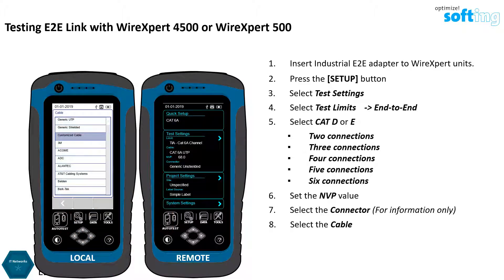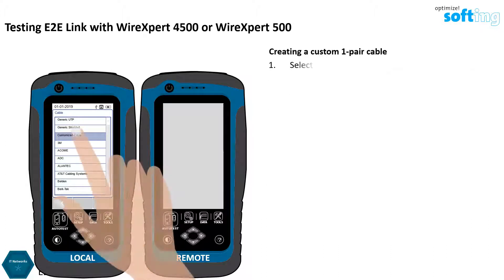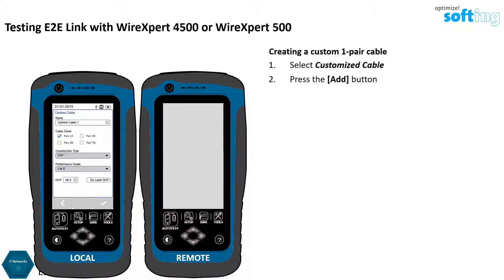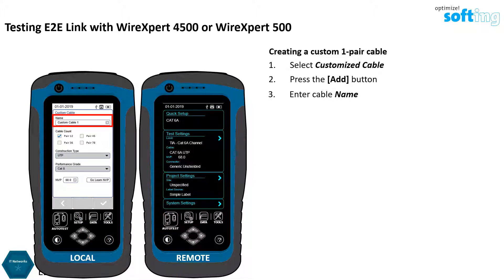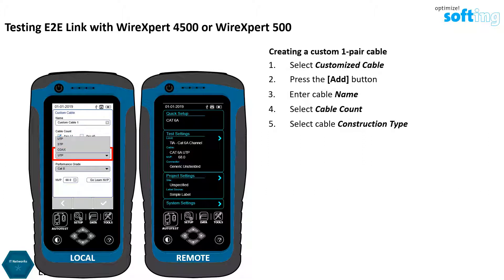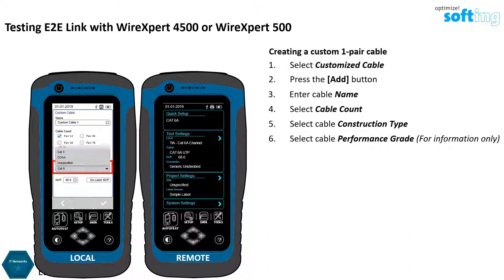The limit sets are dependent on the number of pairs in the cable to be used. 2-pair configurations can be found in Generic UTP and Generic Shielded options. A 1-pair configuration can be created as a custom cable by selecting Customize Cable and selecting Add. Enter the name of the custom cable, then select the pairing that will be used. If a 2-pair cable has to be created, select Pairs 1, 2, and 3, 6 for RJ45 and M12 D-coded Connectors. Select if the cable is a shielded or unshielded construction, then select the cable type. This selection has no influence on the test results, but it will be documented in the test report.